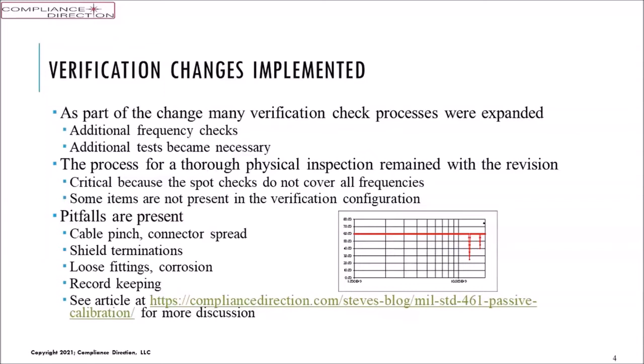And also, there's a possibility of record keeping deteriorating, that we don't know when we last checked such and such probe, such and such cable. So we need to put into procedures, when we adopt this verification check in lieu of calibration, that the record keeping should be used somehow to identify when we do these things. And just putting that we did the cal check in the report, without identifying onto the records for a particular probe or whatever, we don't have an easy way to find out when we last knew it was working good. So that's discussed in that article.